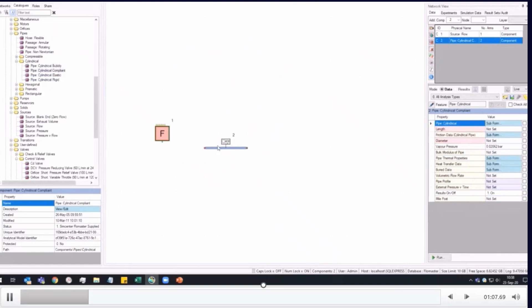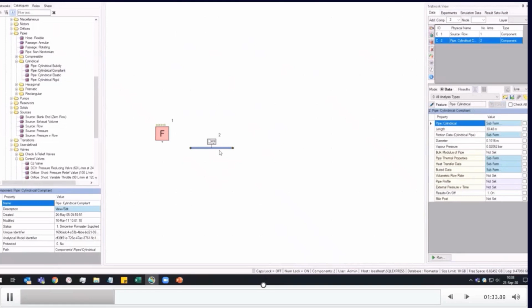And then less intuitively, we do need to give some internal friction information, so things like a roughness. So I'm just going to give a very low roughness, and that's going to drive what the pressure loss through this particular component in the Flomaster network is going to be.